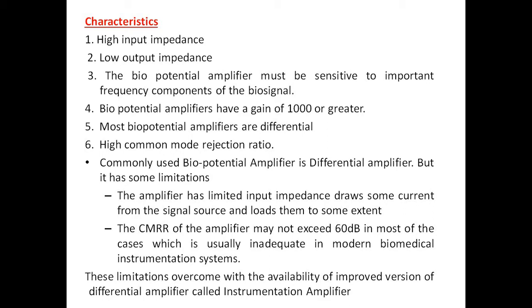The commonly used biopotential amplifier is a differential amplifier. We already said that most biopotential amplifiers are differential. However, it has some limitations: the amplifier has limited input impedance, draws some current from the signal source and loads it to some extent. The CMRR of the amplifier may not exceed 60 dB in most cases, which is usually inadequate in modern biomedical instrumentation systems.